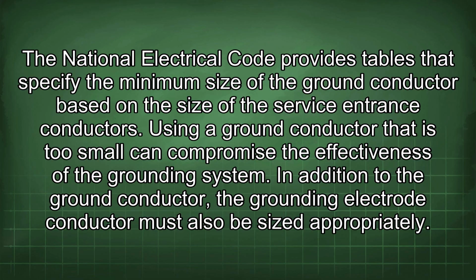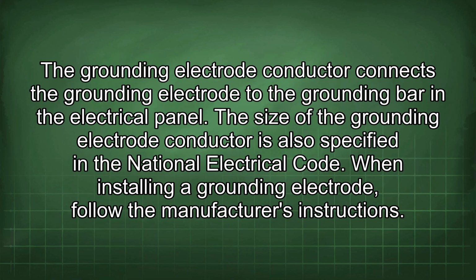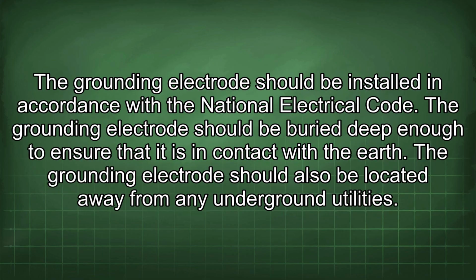In addition to the ground conductor, the grounding electrode conductor must also be sized appropriately. The grounding electrode conductor connects the grounding electrode to the grounding bar in the electrical panel. The size of the grounding electrode conductor is also specified in the National Electrical Code. When installing a grounding electrode, follow the manufacturer's instructions. The grounding electrode should be installed in accordance with the National Electrical Code. It should be buried deep enough to ensure that it is in contact with the earth. It should also be located away from any underground utilities.